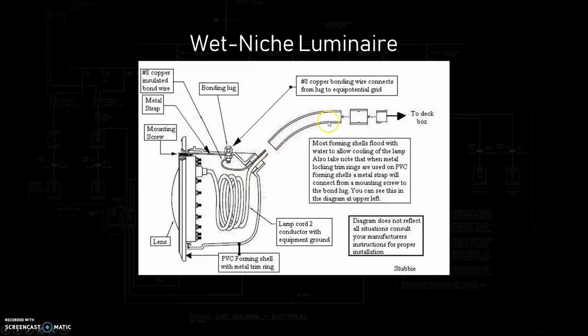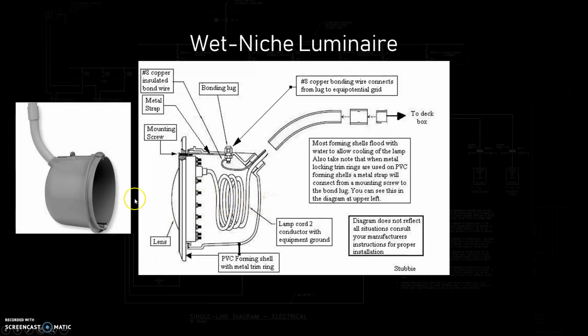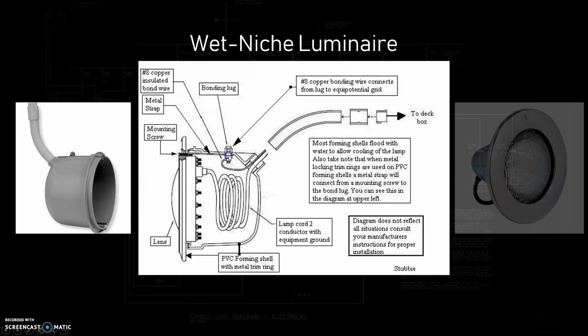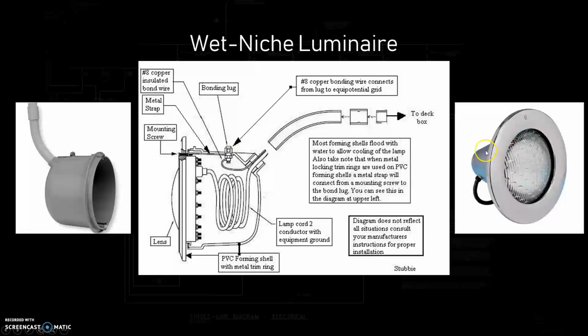It is important when you're connecting this conduit to make sure it terminates higher than the level of the pool. Otherwise, that becomes what? A drain. So it's something you may not think of, but this conduit needs to terminate higher than the pool water level. And here are some photos. Here's a photo of the back box. You can see the conduit coming into it. And this is a picture of your totally sealed light. It reminds me a little bit of a car headlight for some reason, but this is all one unit. It's not meant to be taken apart by the electrician.